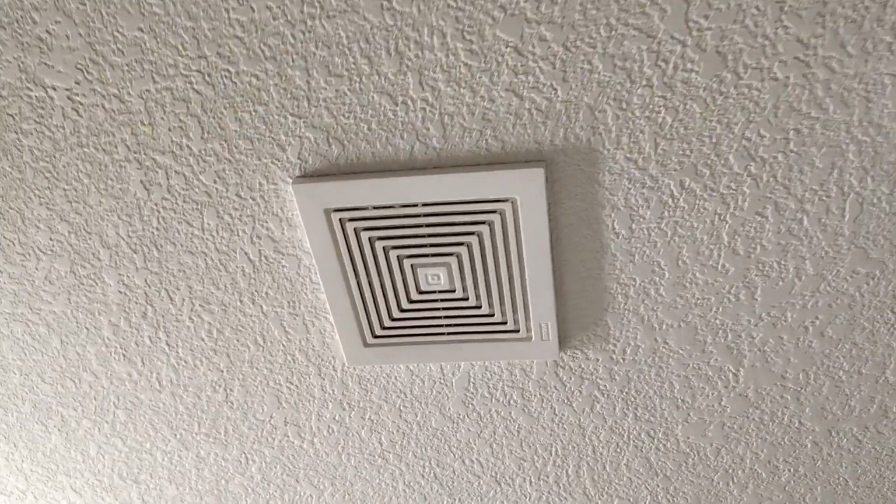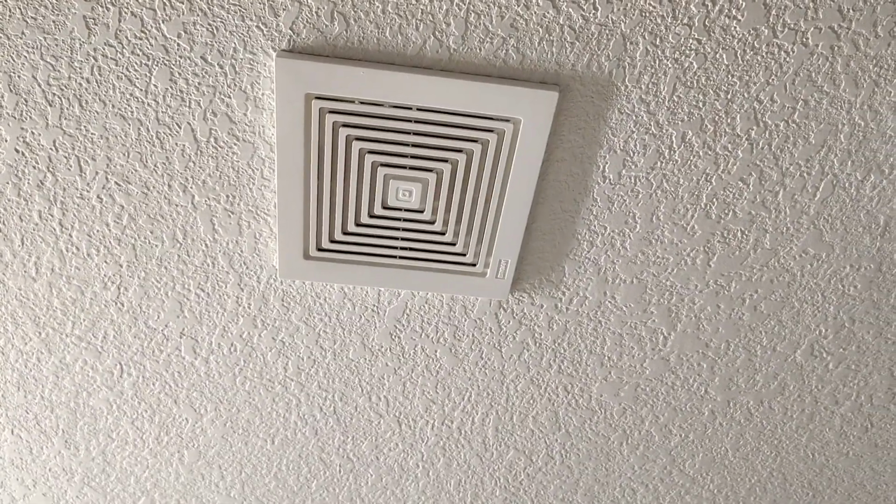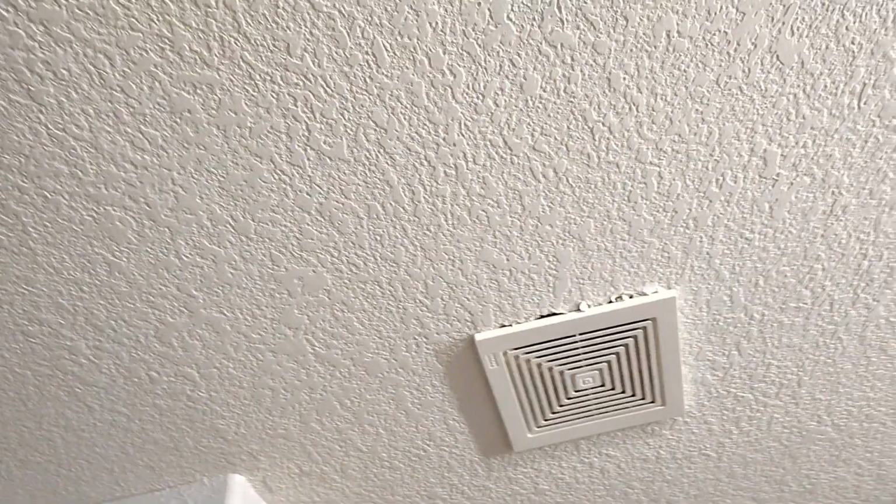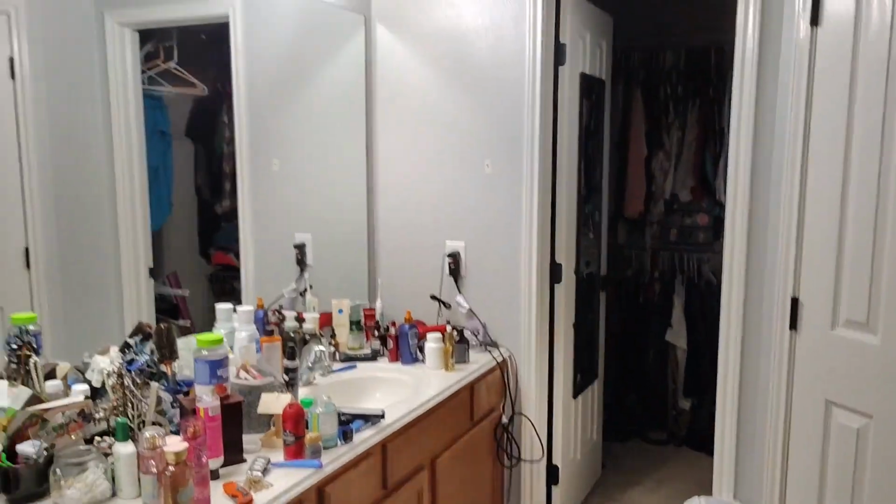So like I mentioned, this exhaust fan is only a 50 CFM. That's cubic feet per minute. And there's another 50 CFM exhaust fan inside this toilet area. So this is another 50 CFM. Together it's 100 CFM, but if you've got this exhaust fan running on its own, and this door is shut, even if this exhaust fan is running, you're not going to be getting rid of all the humidity in this big space. So what do we need to do?